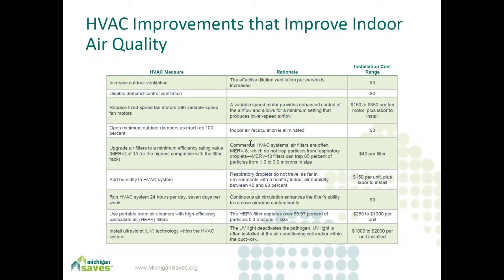One thing to note, however, is that if you are increasing outdoor ventilation, doing all the other improvements that Sonya suggested to bring in more outdoor air, you probably don't need UV technology because you're just going to be cleaning outdoor air at that point. So think about UV technology and whether it's a good option for you. In some cases, it may not be. If you're able to increase the outdoor ventilation, UV technology may not be your best choice. But if you can't do a lot of that, and you have to recirculate a lot of air, then maybe UV technology is a good option for you to look into.